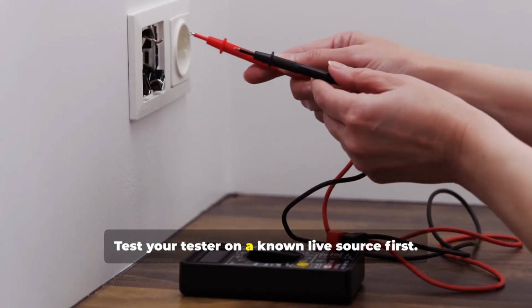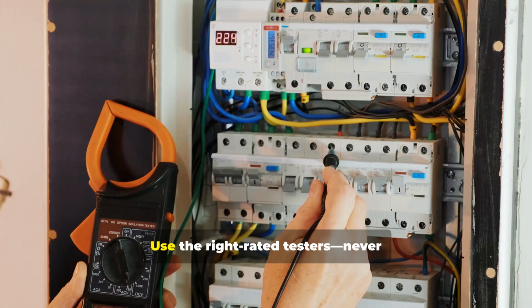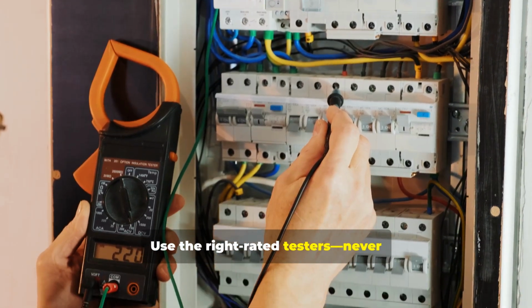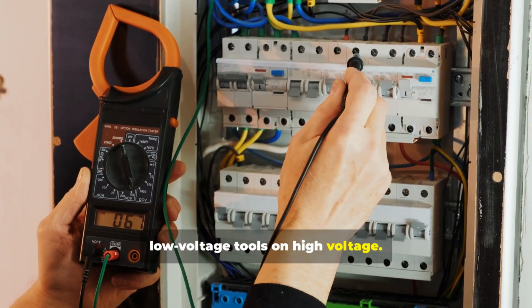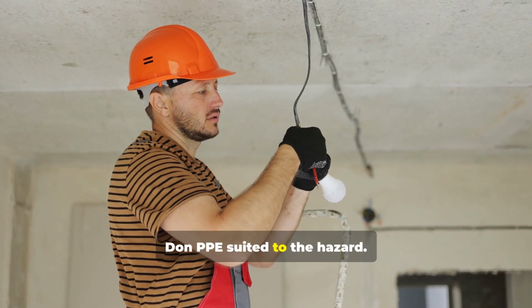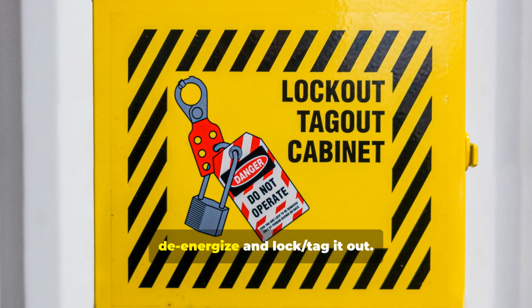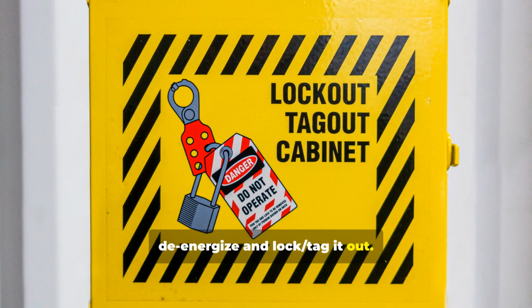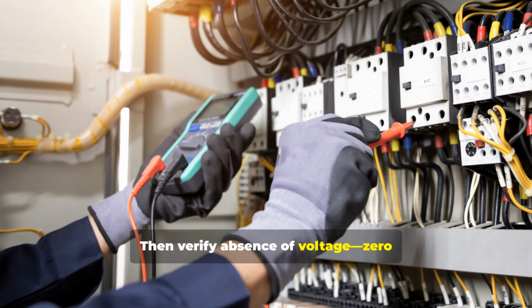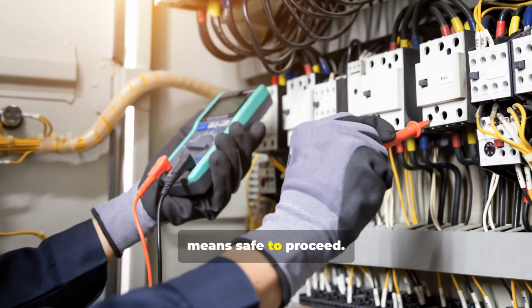Test your tester on a known live source first. Use the right rated testers, never low-voltage tools on high voltage. Don PPE suited to the hazard. If live, de-energize and lock, tag it out. Then verify absence of voltage. 0 means safe to proceed.